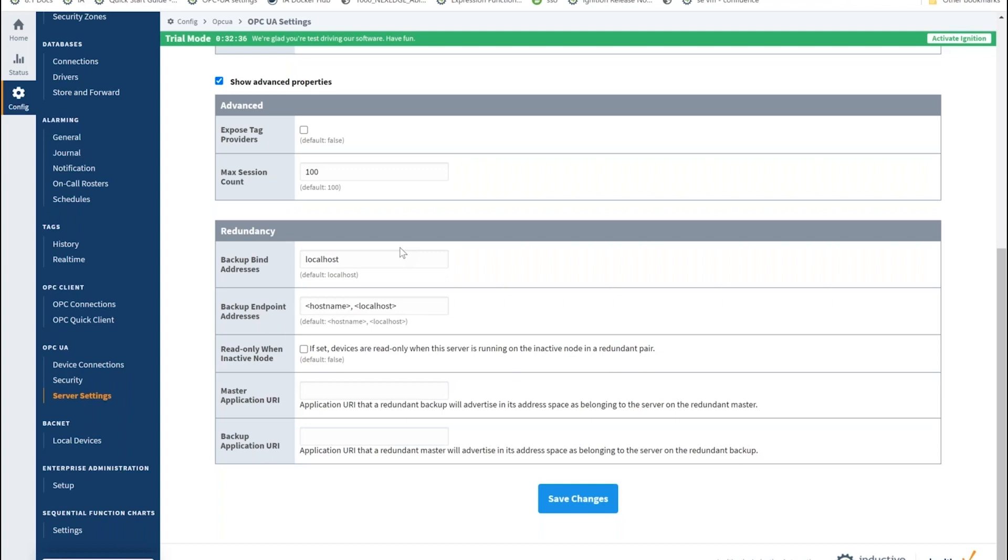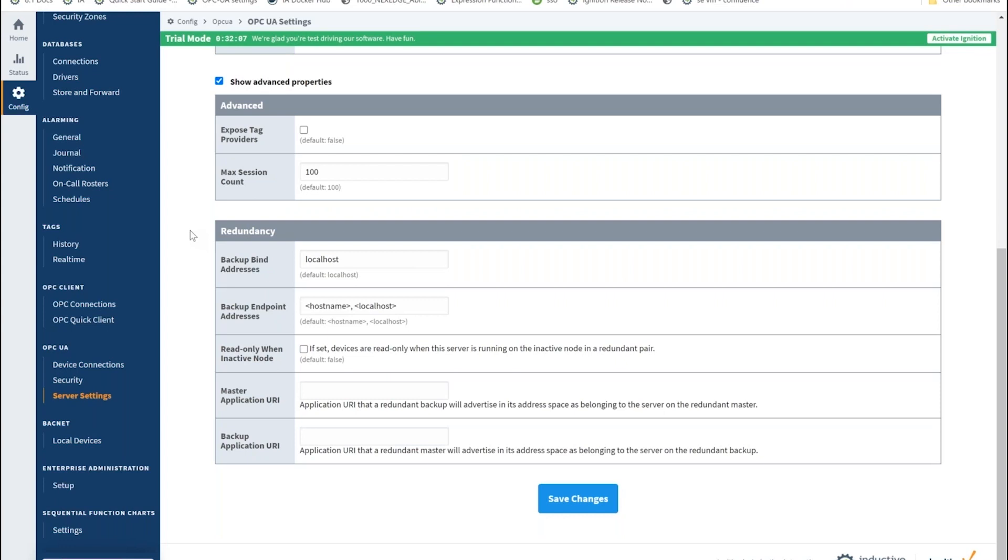It is tied to OPC servers that we are connecting to. For example, there's a number of different external software packages that have OPC servers that Ignition might be making an OPC UA connection to. Those servers potentially can implement that OPC UA spec that has the redundancy between the master and the backup that they have inside there. Those redundancy settings identify where the two different servers are. When the Ignition client is connecting to those, then it will automatically switch over from the main one to the backup one if it loses connection with the main one, and it now understands those pieces of the OPC spec.